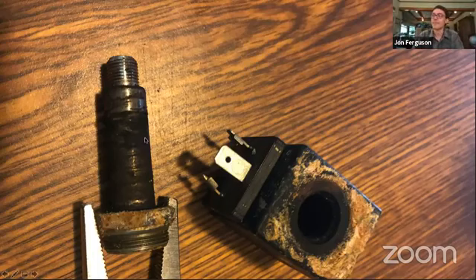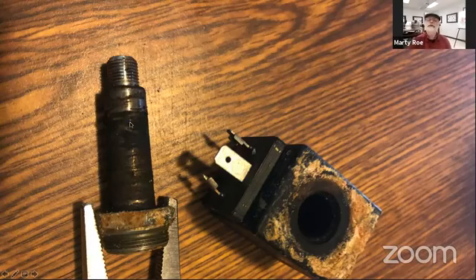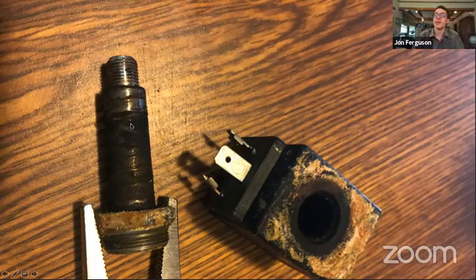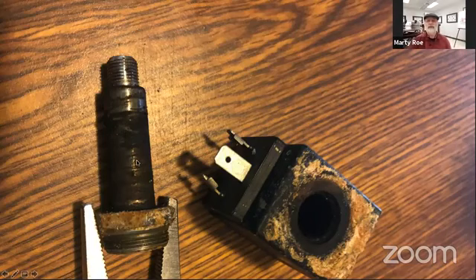I don't know if you see my arrow cursor, but on another valve assembly recently off of a machine, this thing was leaking. There was a little pinhole right there, and a little drip of water coming out. I was wondering what caused that: was it the manufacturing of the stem valve, or was it water, electrical, or magnetic, or what would cause a stem valve to start bleeding out of a little cracked pinhole? Well, obviously there could be some manufacturing defect within the metal, maybe an impurity that caused it to deteriorate and create that pinhole. The other possibility is that metal is pretty thin right there.